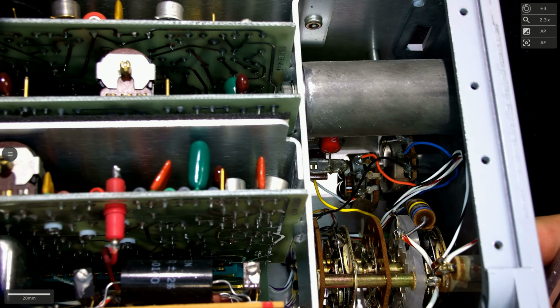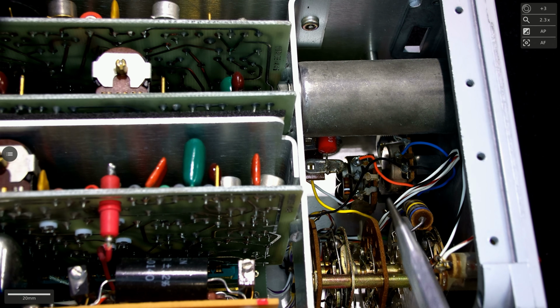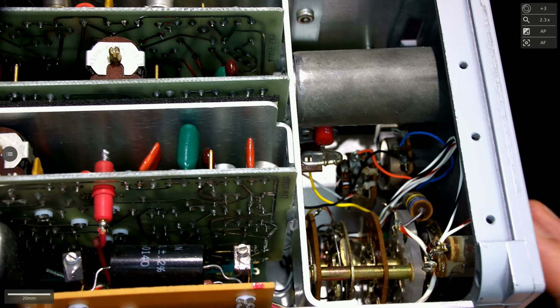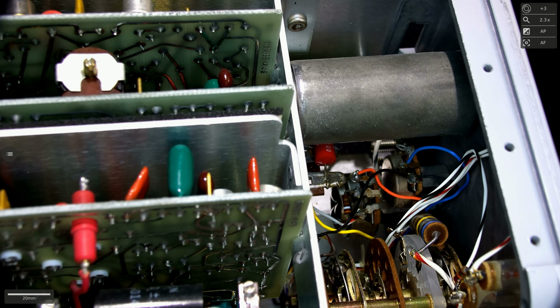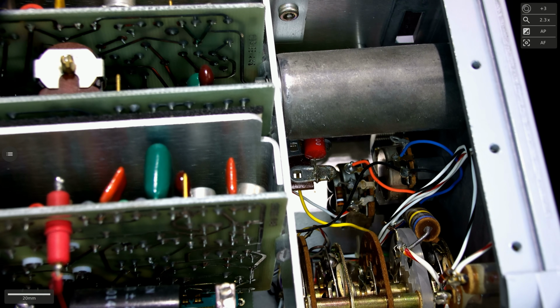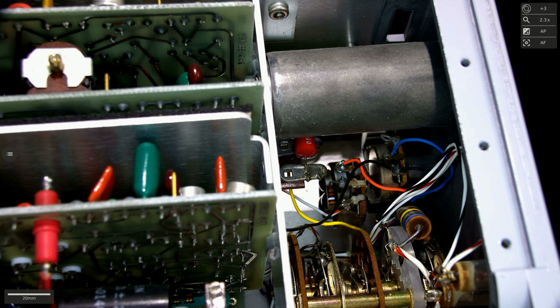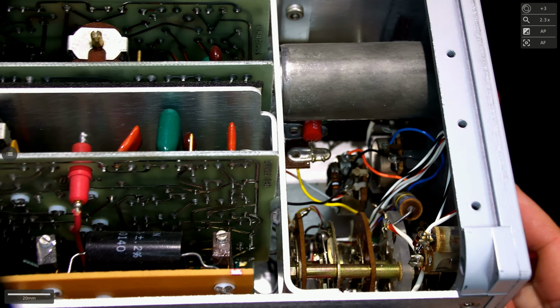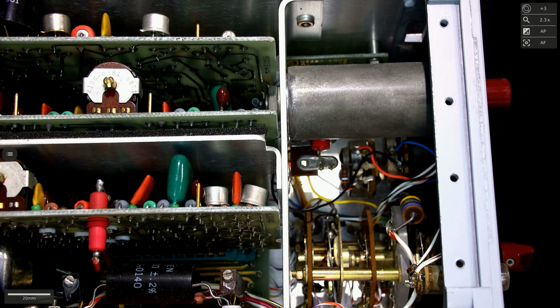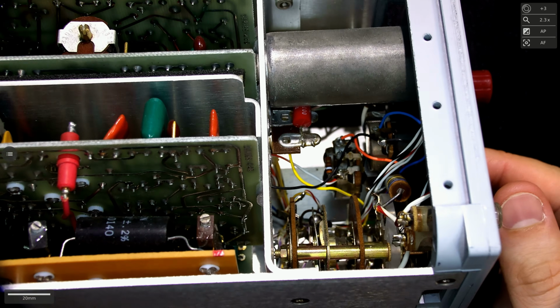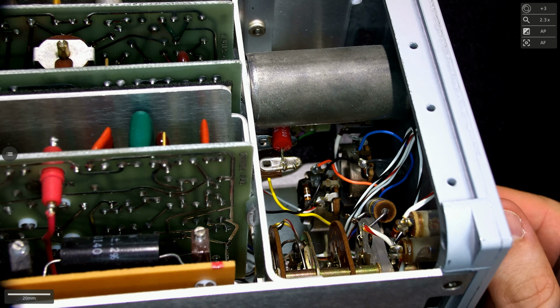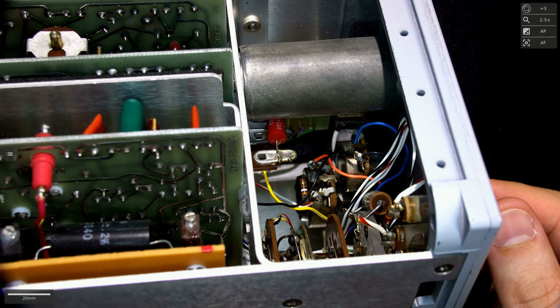And there's two potentiometers in there worth paying attention to. So this potentiometer is our zero adjustment. And the one underneath it, if you look carefully, there are 3 ball bearings buried down in there. This is a really interesting design. So those ball bearings make up a planetary gear system, which means that you can then adjust that potentiometer in a much finer way with the same one-turn potentiometer.